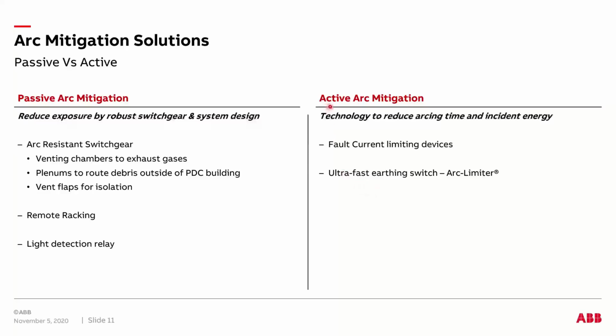On the other hand, we have an active arc mitigation technology, where some of the examples are fault current limiters or the ultra fast earthing switch, as I mentioned, or the high speed grounding switch, which has the trade name arc limiter. Using the active arc mitigation technologies, we are actually eliminating the arcing event within less than 5 milliseconds. Comparing 5 milliseconds to 80 to 100 milliseconds, it's a significant difference where, in addition to protecting your personnel, you can also protect the equipment. So your downtime, if an arcing fault occurs, significantly reduces.